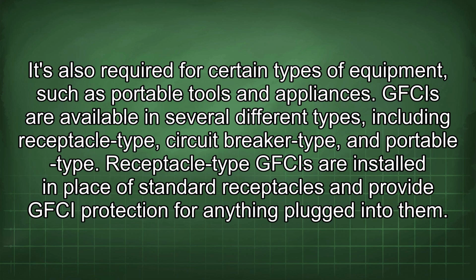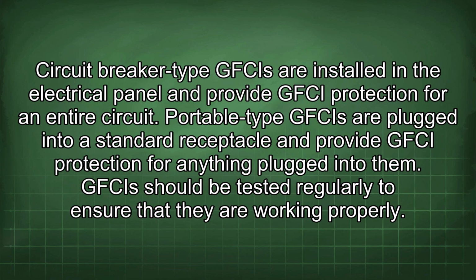GFCIs are available in several different types, including receptacle type, circuit breaker type, and portable type. Receptacle type GFCIs are installed in place of standard receptacles and provide GFCI protection for anything plugged into them. Circuit breaker type GFCIs are installed in the electrical panel and provide GFCI protection for an entire circuit. Portable type GFCIs are plugged into a standard receptacle and provide GFCI protection for anything plugged into them.